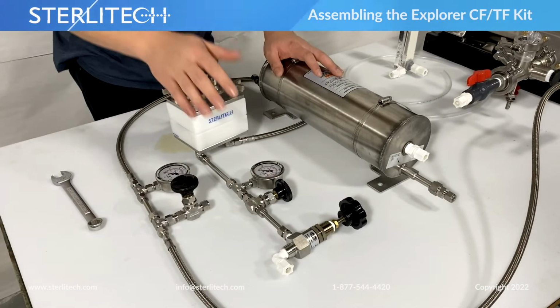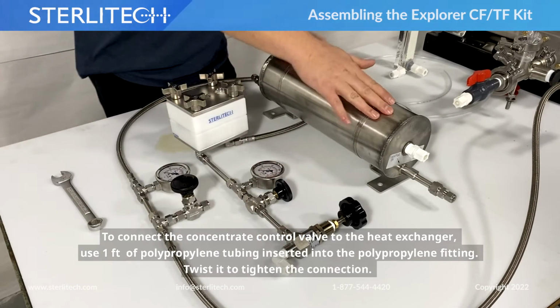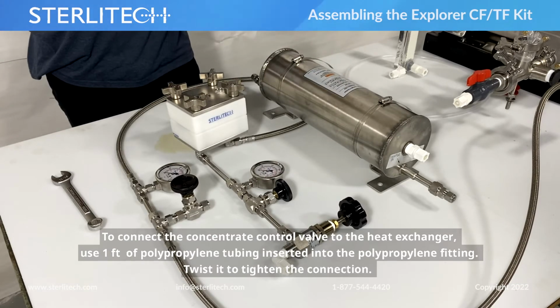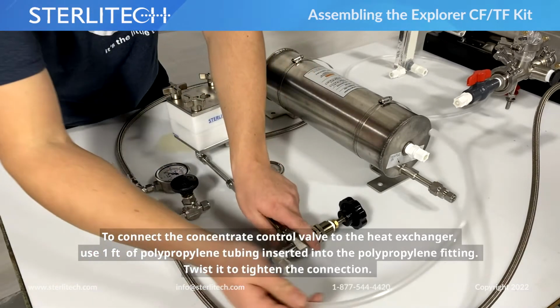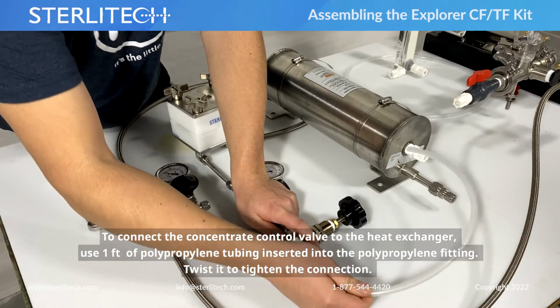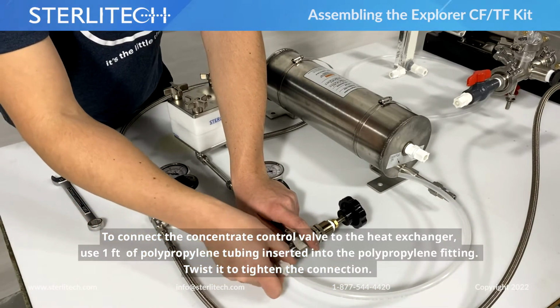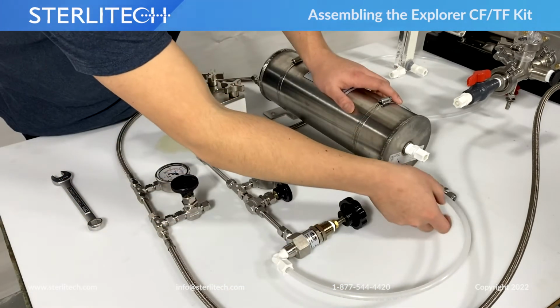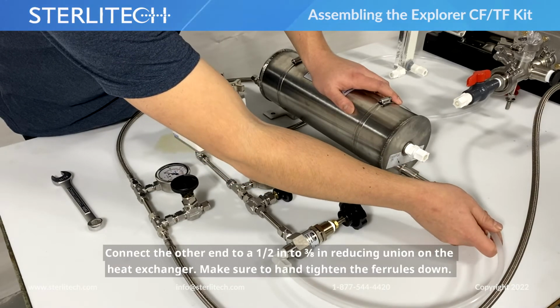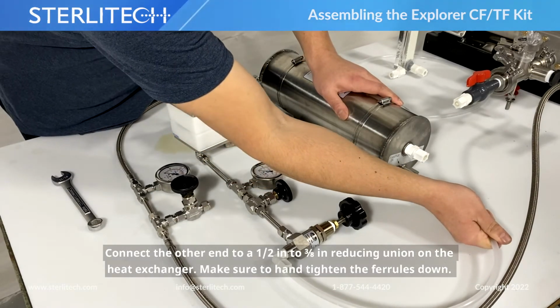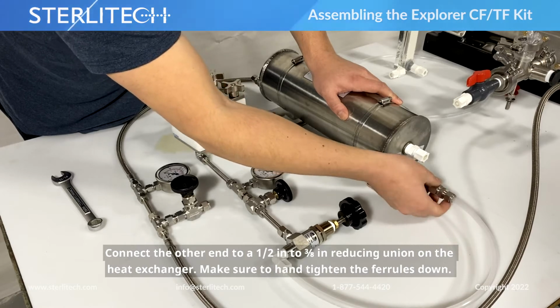Alright, next up we're making the connection from our concentrate control valve to our heat exchanger. I'm going to use about 1 foot of polypropylene tubing. I'm going to connect that into this polypropylene fitting, just twist it to tighten it down. The other end we're going to connect into a 1/2 inch to 3/8 reducing union on the heat exchanger. Just make sure you tighten those ferrules down.